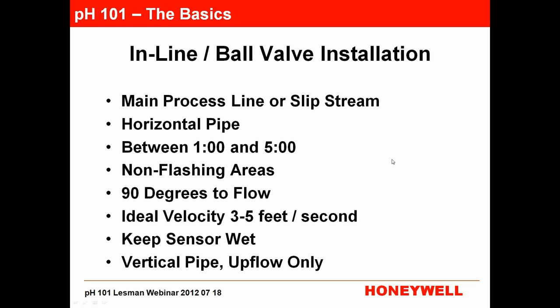If you have to use a vertical pipe installation, do it as upflow only. In a downflow pipe, there can be periods with no flow causing drying. More commonly, in a downflow pipe you can't guarantee the pipe is full, leading to water hammer — instantaneous periods of no flow and then surge — which beats up your pH sensor. A pH sensor is essentially a laboratory device that we keep trying to make more able to withstand the rigors of process, so try not to damage it unnecessarily.